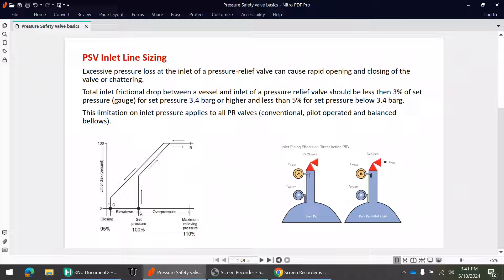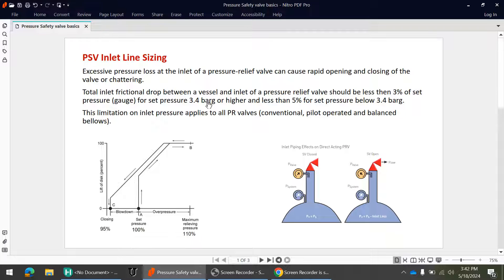API 520 Part 2 says that the total frictional pressure drop between the vessel nozzle and the inlet flange of the PSV should not exceed 3% of the set pressure in gauge. If there is a low set pressure PSV with a set pressure less than 3.4 bar gauge, then you can exceed the inlet line pressure drop up to 5% of set pressure, but generally it is better to follow the 3% criterion.